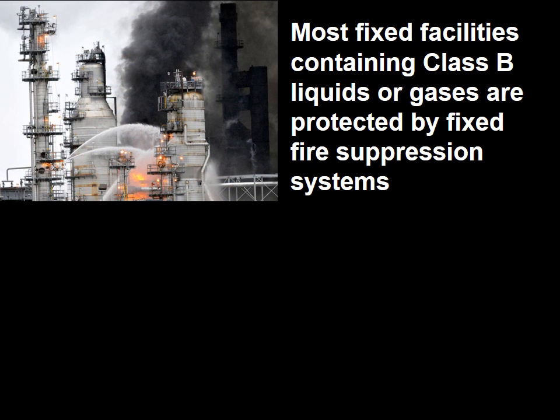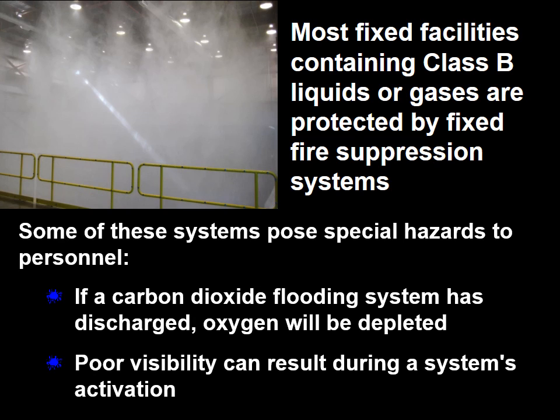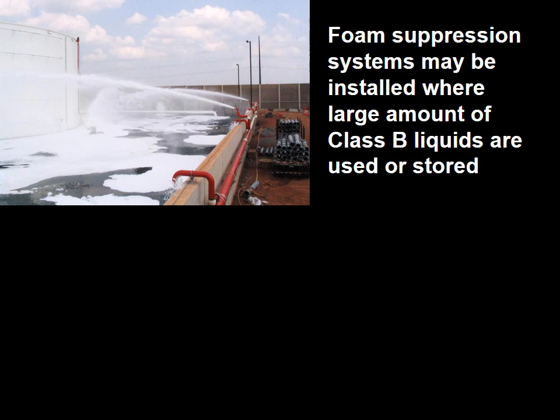Most fixed facilities containing Class B liquids or gases are protected by fixed fire suppression systems. Some of these systems pose special hazards to personnel. If a carbon dioxide flooding system has been discharged, the oxygen will be depleted, and poor visibility can result during activation as well.